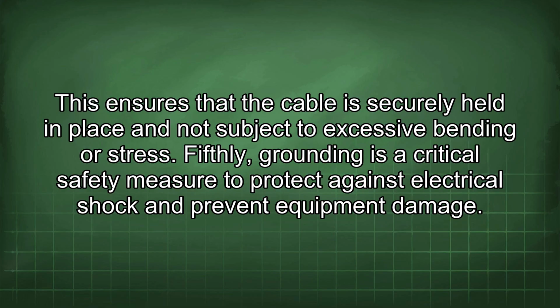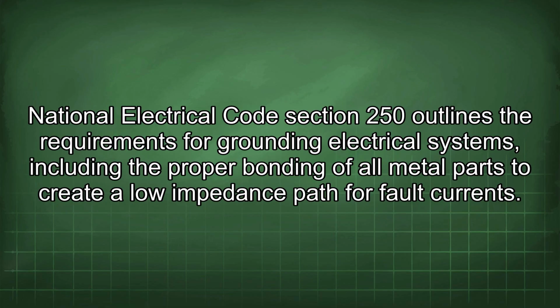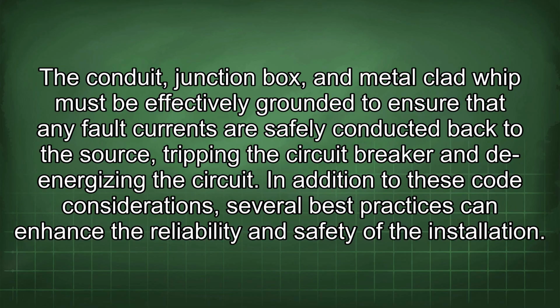Fifthly, grounding is a critical safety measure to protect against electrical shock and prevent equipment damage. National Electrical Code Section 250 outlines the requirements for grounding electrical systems, including the proper bonding of all metal parts to create a low impedance path for fault currents. The conduit, junction box, and metal-clad whip must be effectively grounded to ensure that any fault currents are safely conducted back to the source, tripping the circuit breaker and de-energizing the circuit.